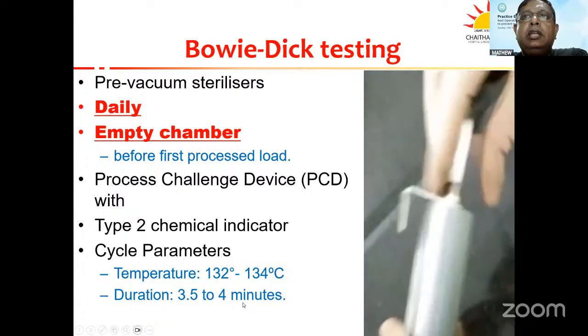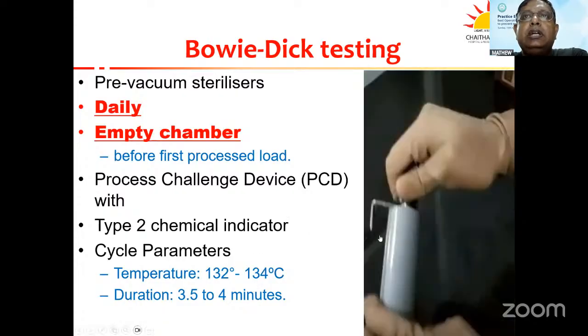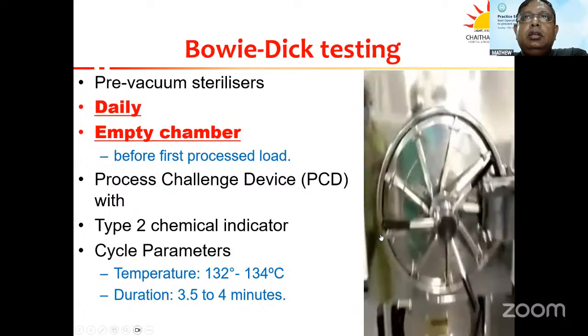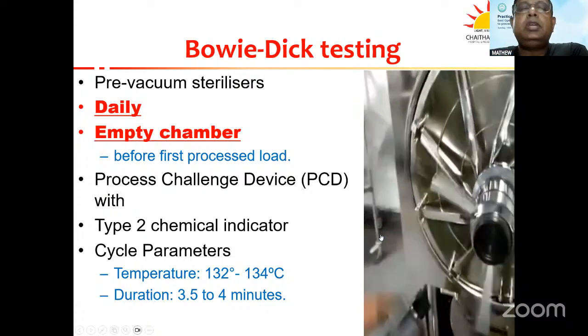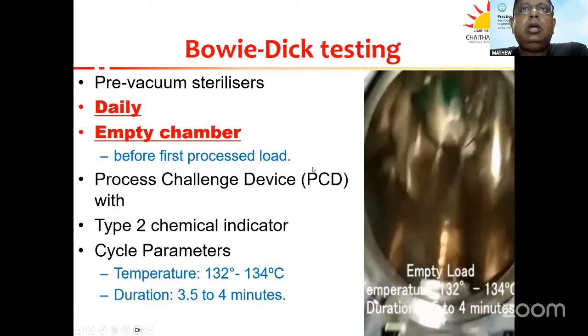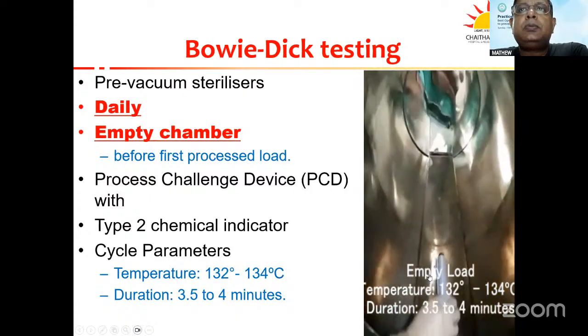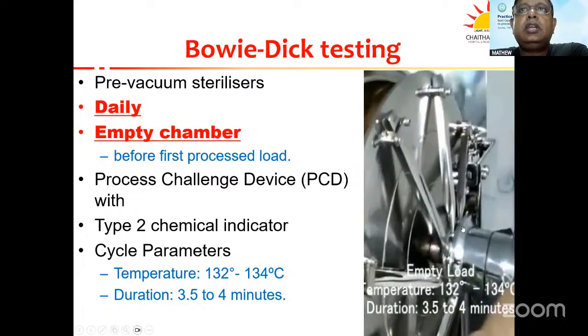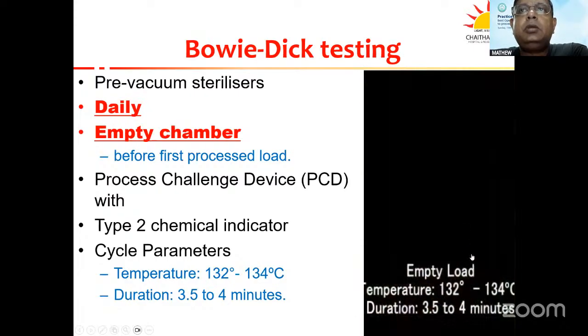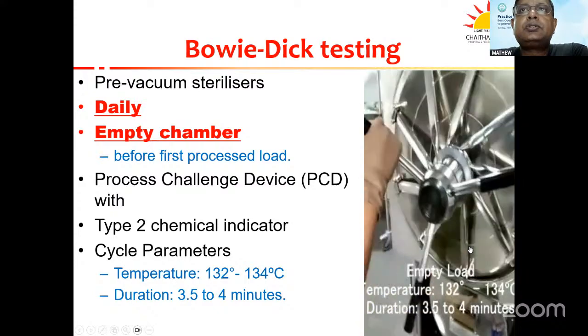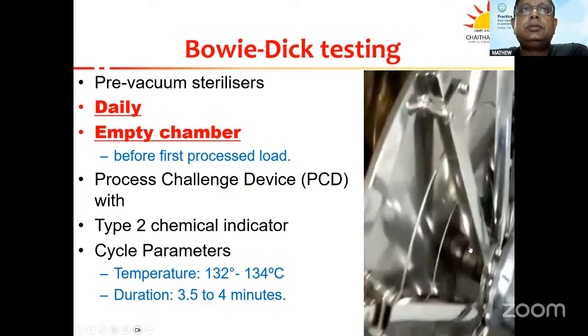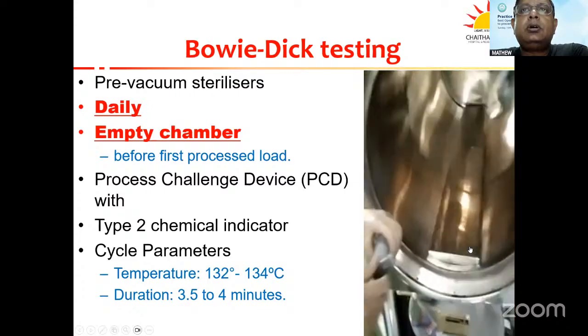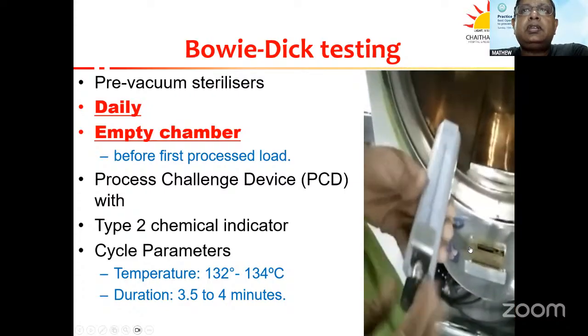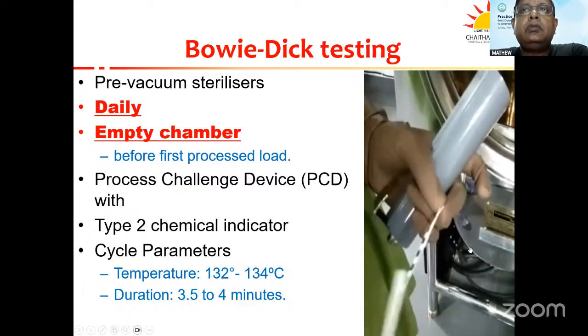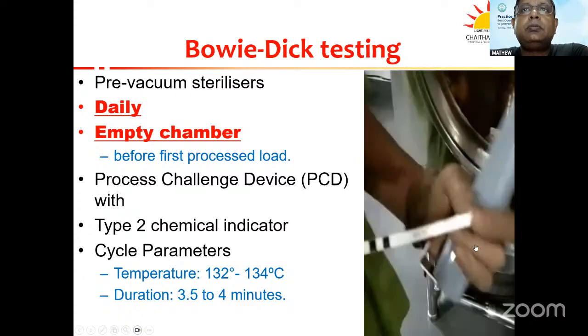And by the end of that cycle, when we remove that, it should have changed from yellow to black. So it is much more, just place it at the bottom of the autoclave, empty load. And then at the end, once it is cooled down, we can take it out and it should be changed all to black. If this has changed to black, then only we should do our load for the day. And you can see that this is all black, and then it is safe to proceed for the day.